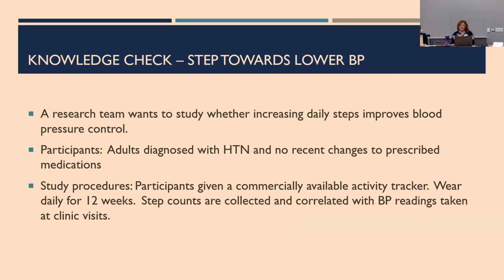So a research team wants to study whether increasing daily steps improves blood pressure control. They're doing this for adults diagnosed with hypertension with no recent changes in prescribed medications. They're giving these participants a daily activity tracker, like a Fitbit or an Apple Watch or whatever. They're going to wear that daily for 12 weeks. And then the steps are collected and correlated with the blood pressure readings taken in clinic. So do you think this study requires an IDE?